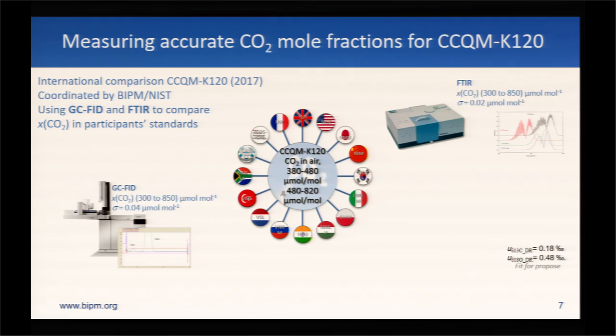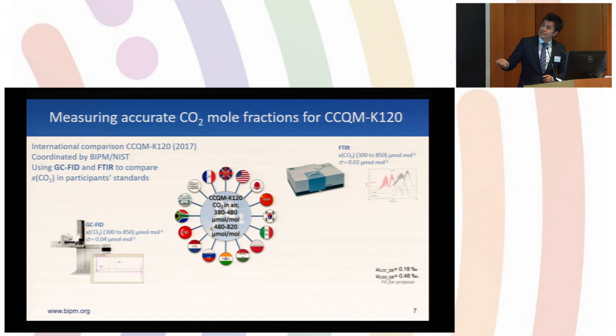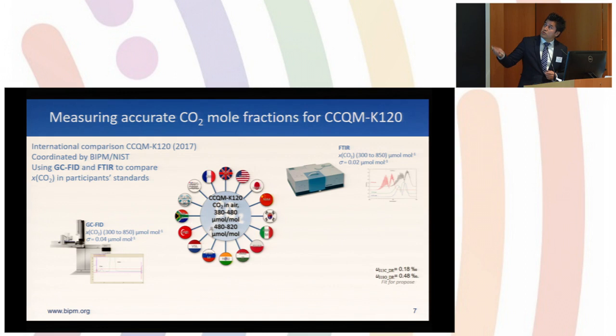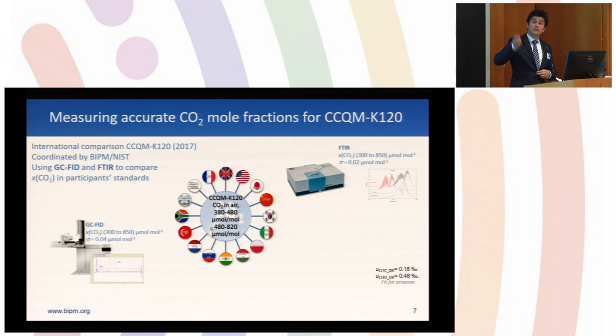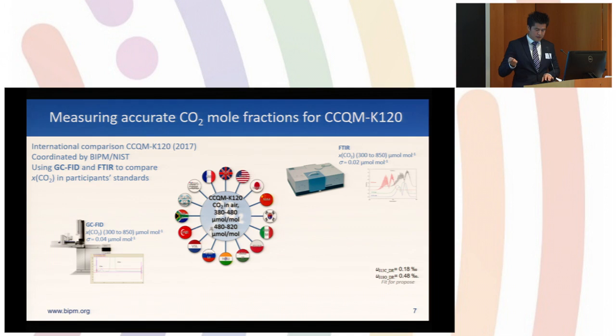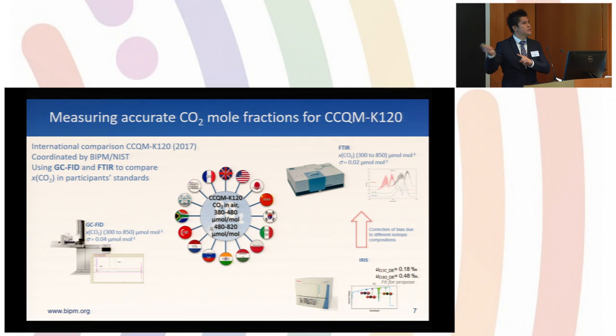Now let me say a few words about the comparison we organized last year. We use a GCFID that is not sensitive to pressure broadening effects or isotopic compositions of the mixtures of CO2, and then we use an FTIR at the same time. More and more laboratories around the world are using these optical systems, so it's very important for everyone to know which are the potential sources of bias. To correct the mismatch between the isotopic composition of each cylinder, we use a delta ray to get the delta value and then correct the FTIR values.